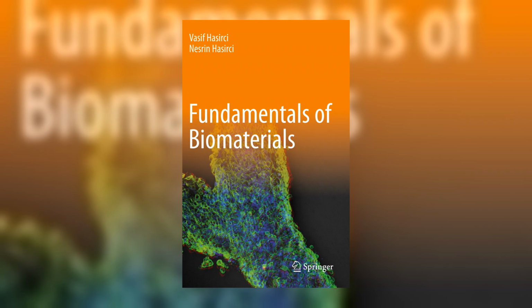Skip them, and a past cytotoxicity result tells you nothing about which substance passed. Same substance, different leaching profile, different biology. A material, for the body, is defined by what it gives off and how its surface presents. Its nominal identity is not what determines its biology.